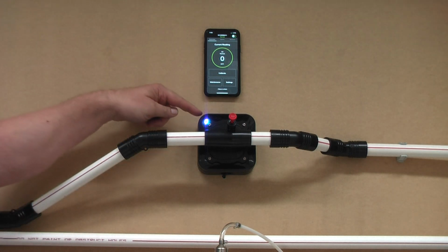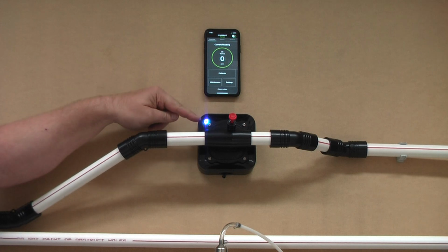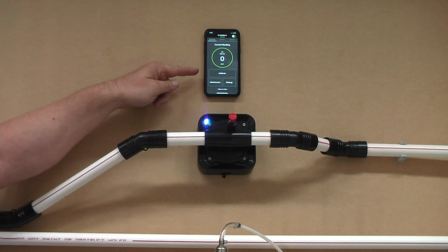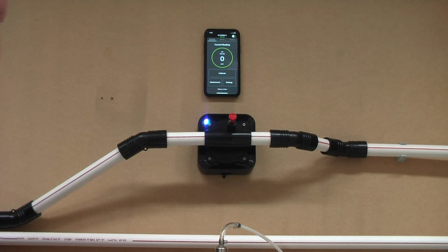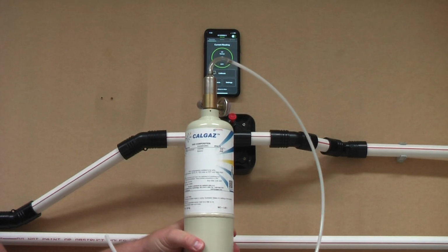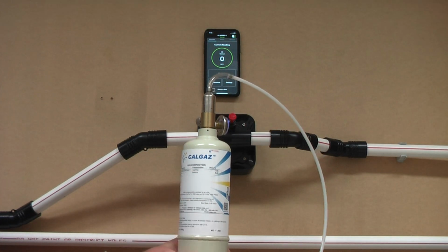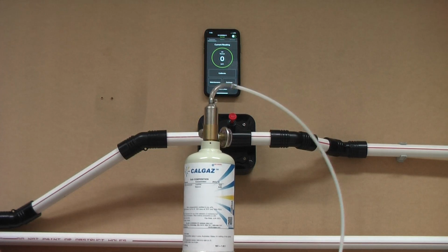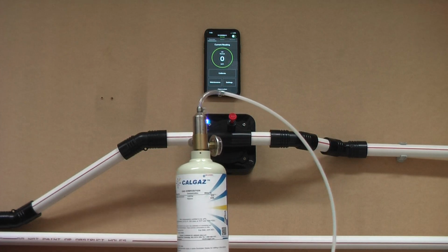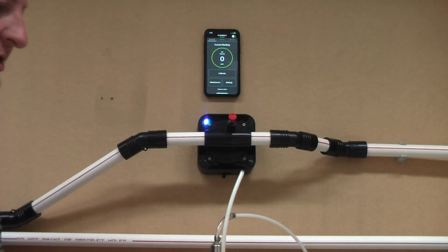We've got the detector installed on the wall as such, connected via Bluetooth to a phone or tablet running the Sensepoint app. We also have a gas bottle with a known concentration of 100 parts per million of CO gas for this particular detector, a fixed flow regulator at half a litre per minute, and a tube with an outer diameter of 6 millimeters.